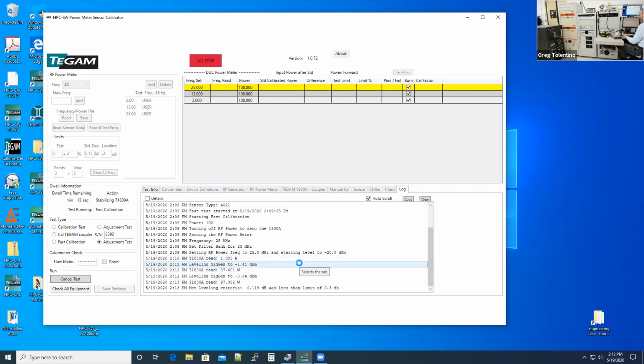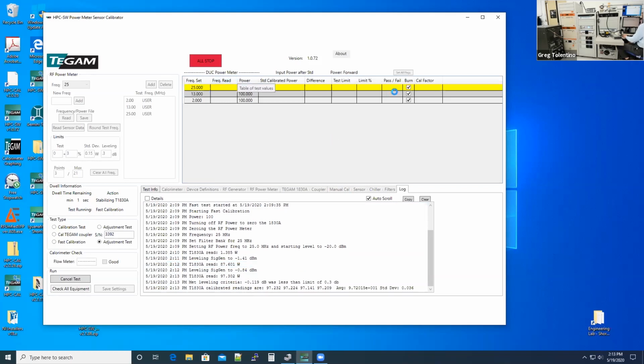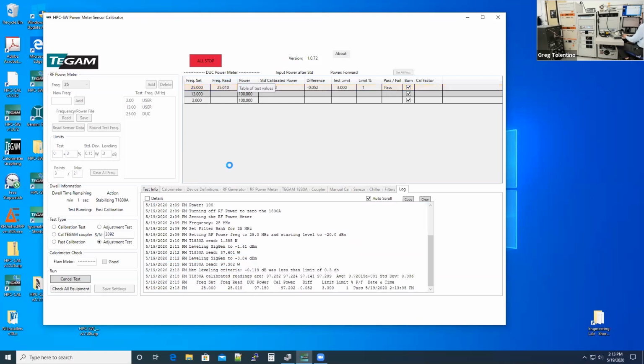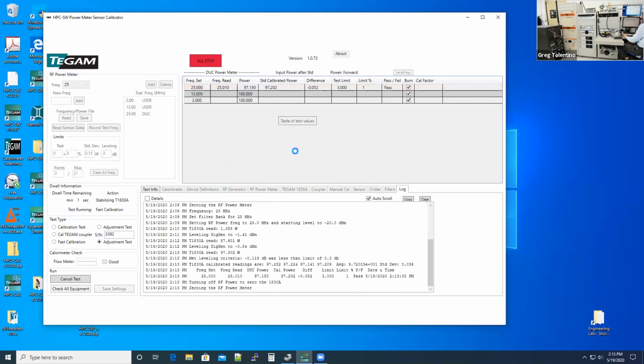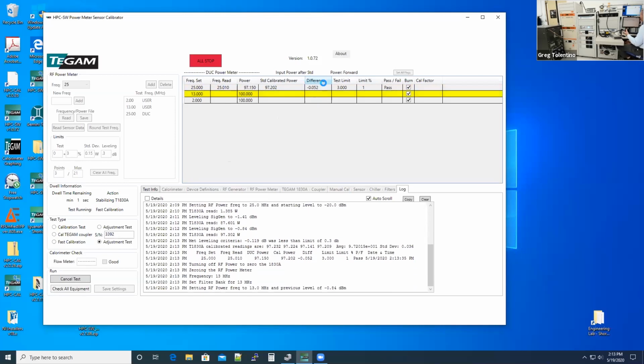Now in 15 seconds, we're going to go ahead and send the command to burn the EEPROM of the Bird. And then as soon as that's set, we'll go ahead and read it back and just verify that that point was burned correctly, and then write the yellow line of the test report. There we go. So we did the 25 megahertz write of the EEPROM. We turned around, read the meter back, and unsurprisingly, there was only 50 milliwatts difference at 100 watts, because that's a brand new calibration, had not had a chance to drift or really do anything wrong yet.